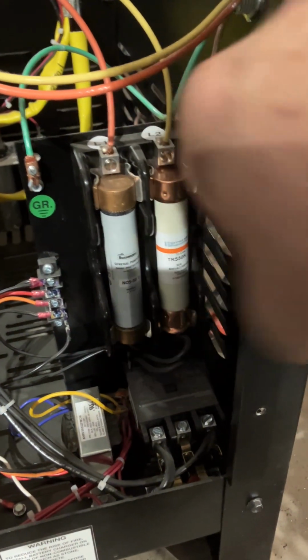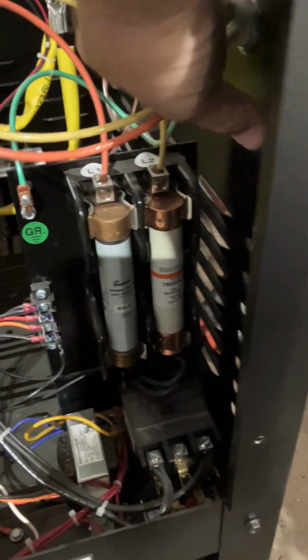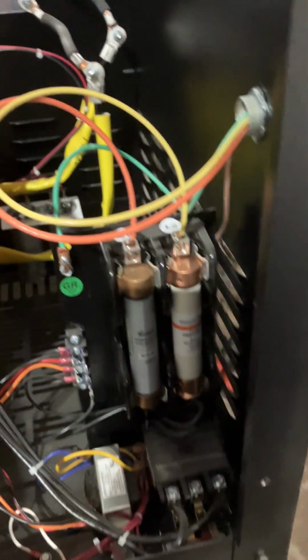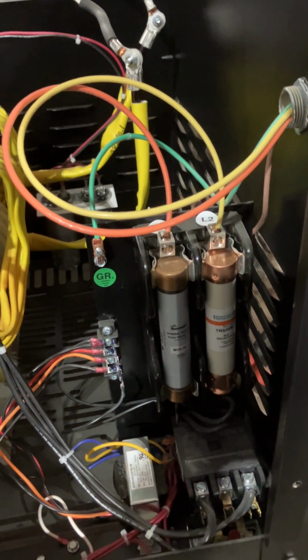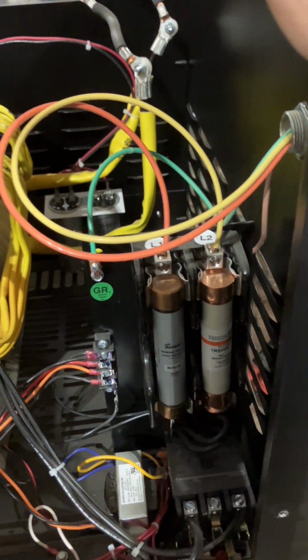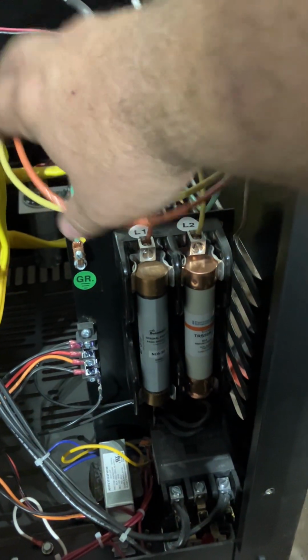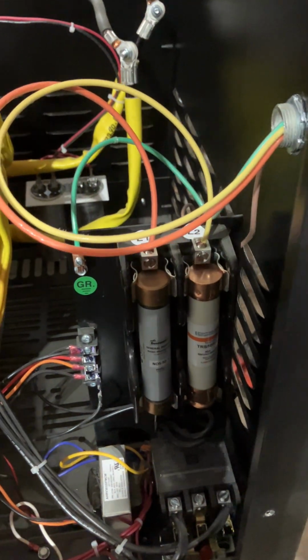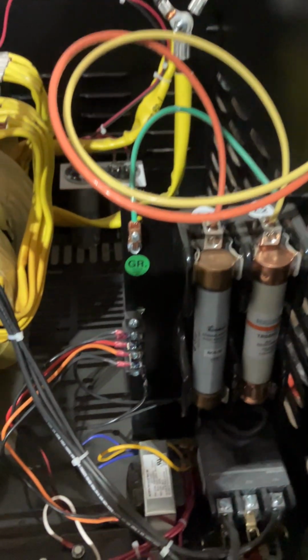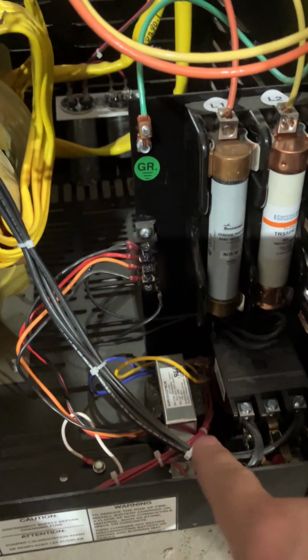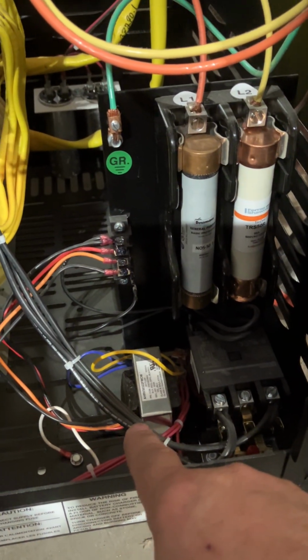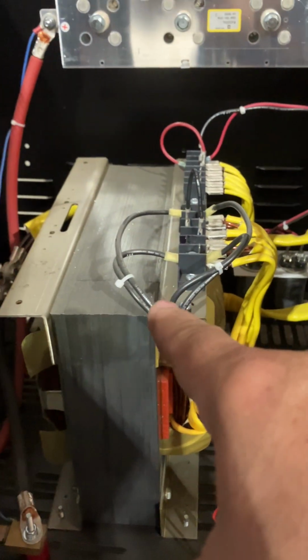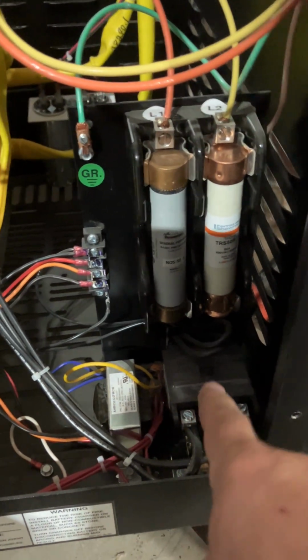Now, here's where we've hooked it up inside the unit. Notice we went ahead and pulled three phases, but since I found that the brown, the A phase in that panel, is pulling a lot more amperage than the other two phases, I went ahead and used the other two phases in this machine to balance it out a little bit. So we've got B phase and C phase in here, and here's the ground. Here is the control transformer right there. And way back there, hard to miss, is the main power transformer. And here you see the contactor that actually turns the thing on.